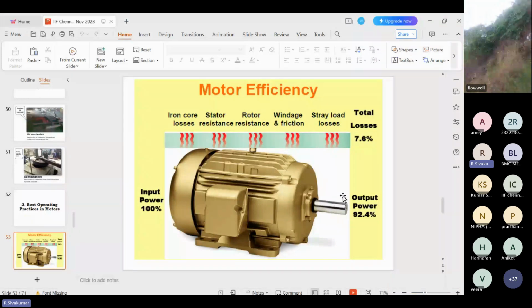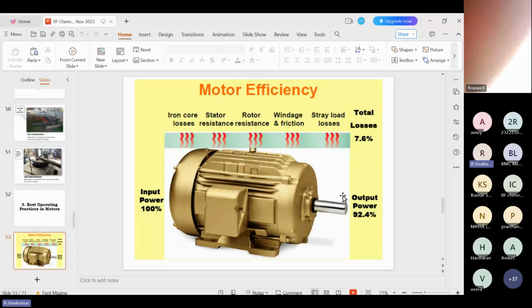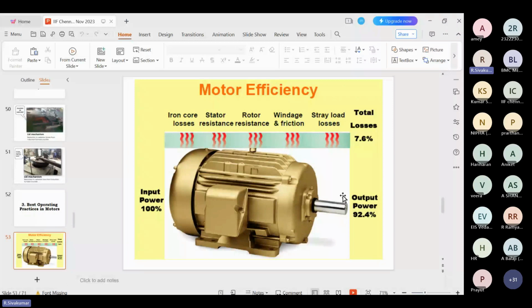Normally in industry, any industry follows the regular practice of motor rewinding. What is the importance of motor rewinding? The moment the motor fails, the coil fails, it is given to the local shop service person. The local workshop removes the stator and the rotor. They do not use the proper gauge of wire, and when the stator and rotor are reassembled, it is not up to the factory mark, because in the factory they use proper tools for assembling the stator and rotor, the air gaps are maintained, and mainly the proper wire gauges are used for the winding, mainly for the stator. But in the market they do not use the proper gauge, which leads to more losses.